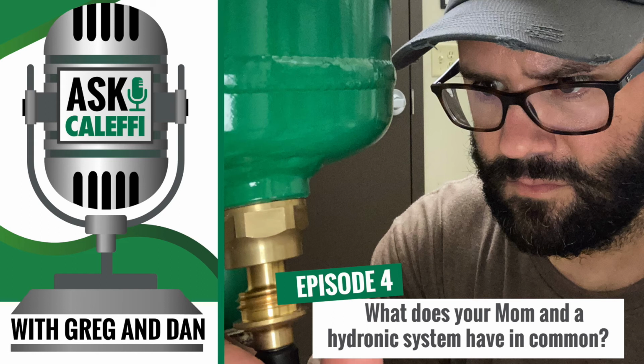Yeah, absolutely. You look at that magnetite, that's almost like a black sludge or tar in the system. Black sand, yeah. Yeah, almost like a sand, right? Mm-hmm. And it's awful on variable speed pumps. Yeah, that's kind of where my mind was going. You talk about the variable speed pumps, and the variable speed drives have little magnets within the drive. So if you don't have some type of magnetic separation in your system, that pump's going to suck that magnetite in.